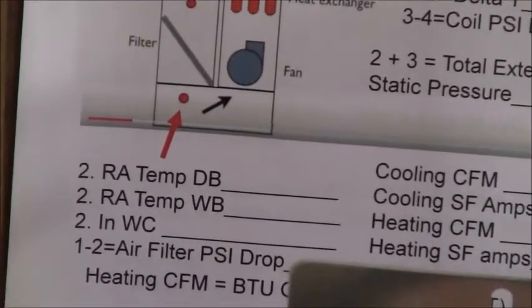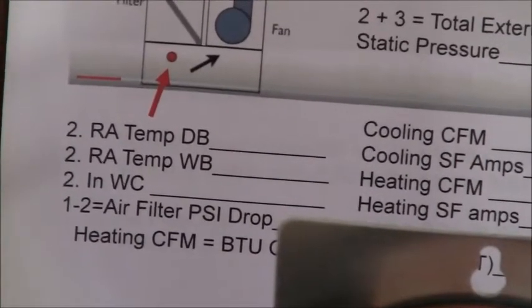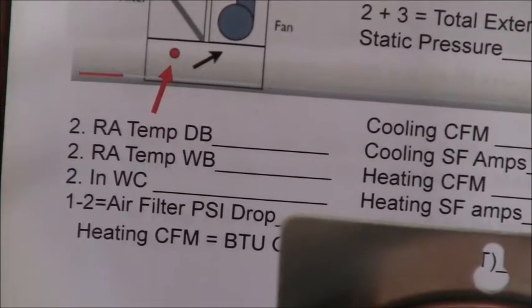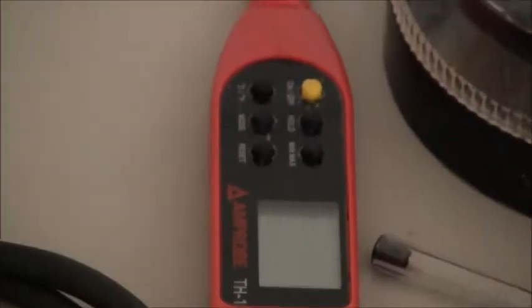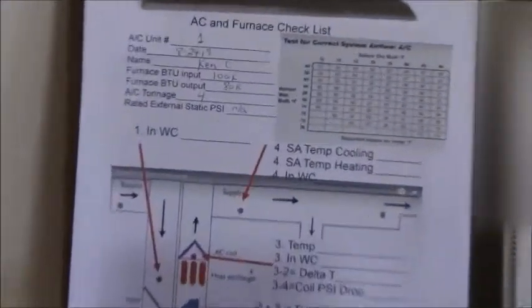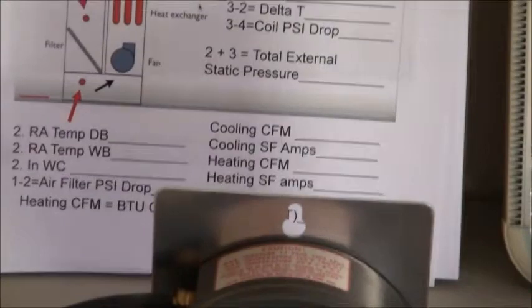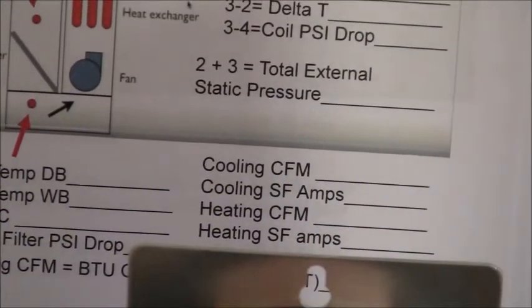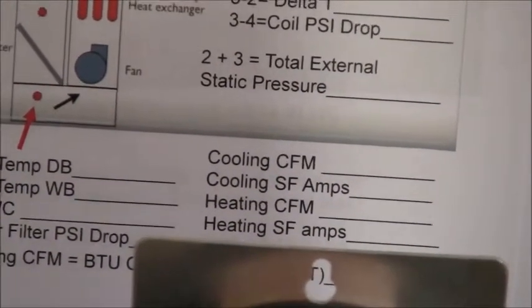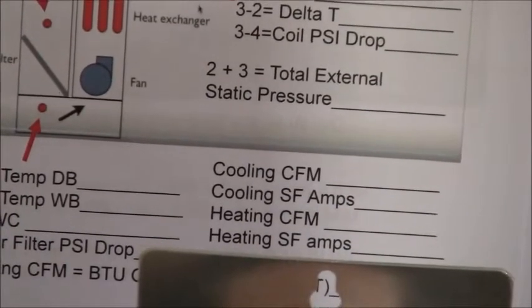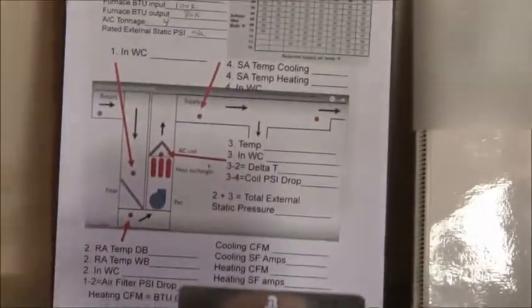And then point number 2, the return air temperature dry bulb and return air temperature wet bulb. I have a special thermometer. Where is it? Right there. This particular thermometer will give us that information when we get to it. So we're going to go through and fill out this checklist and determine the health of the system. We're going to try to figure out our CFMs. Now, the CFMs are a tricky one because I don't have an anemometer. I wish I did, but I don't.